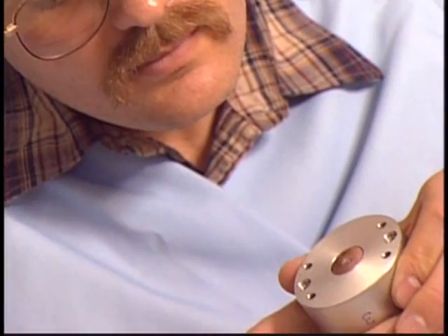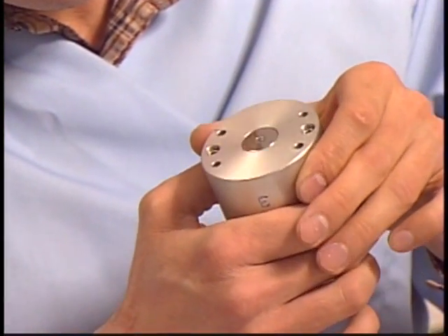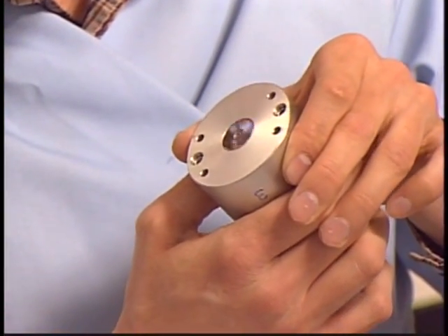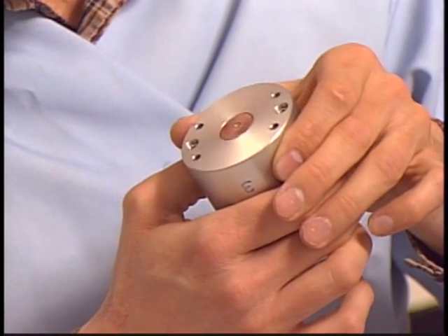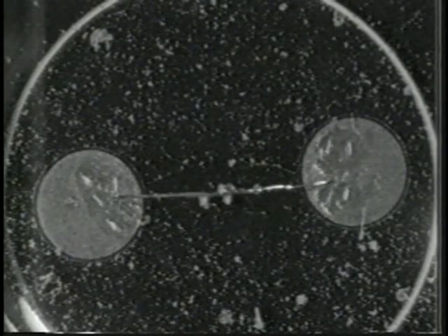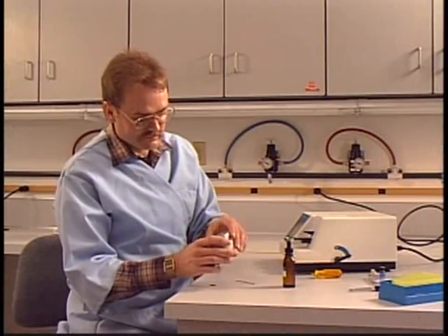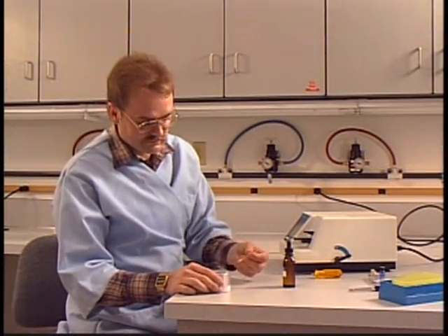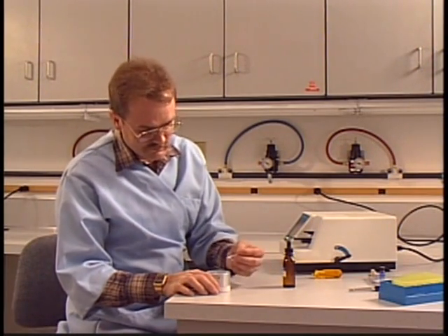Remember, any time the thermocouple head is out of the machine, it's important not to wipe, snag, or otherwise damage the delicate thermocouple. If your thermocouple looks like ours, it may only need a routine cleaning. If it has material caked on, that'll require more drastic cleaning measures. We'll demonstrate those in a few moments. Right now, let's do a simple water rinse. For routine cleaning, that should be all you need.